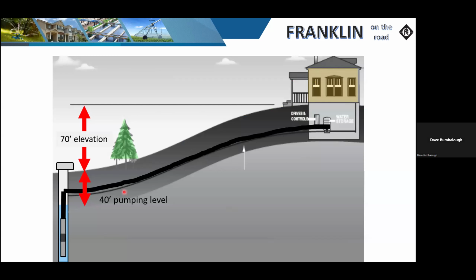Now then, once we get it to the surface, we may have to account for any elevational changes, up or down. If it goes downhill, that's just a plus for us. That means the pump doesn't have to work as much because gravity is going to help us at that point. Where we run into trouble is if we have to lift it up to the application.